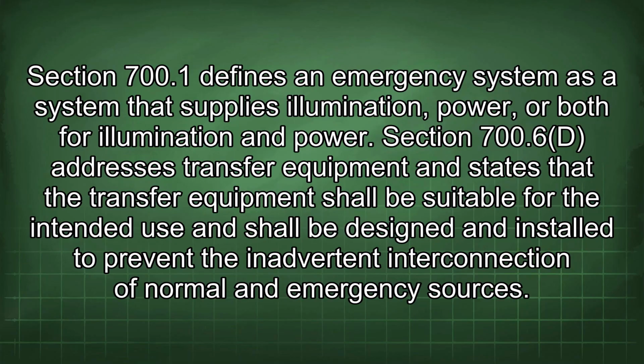Section 700.1 defines an emergency system as a system that supplies illumination, power, or both for illumination and power. Section 700.6d addresses transfer equipment and states that the transfer equipment shall be suitable for the intended use and shall be designed and installed to prevent the inadvertent interconnection of normal and emergency sources.